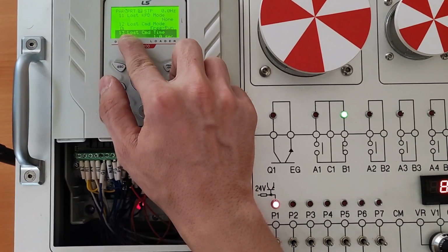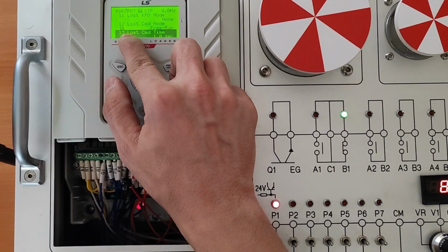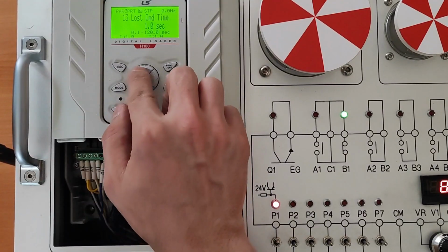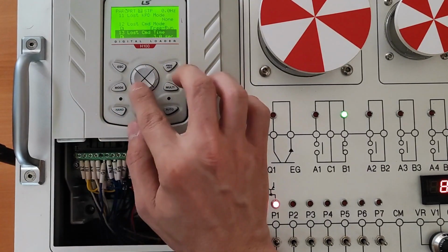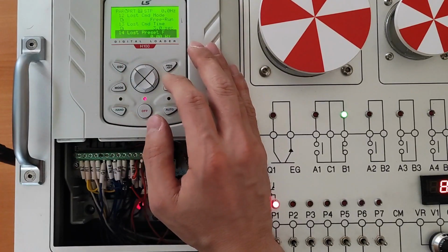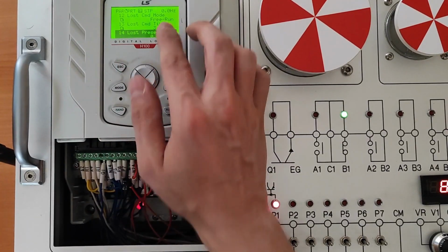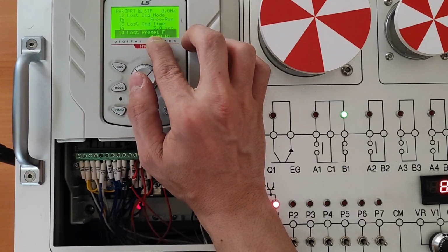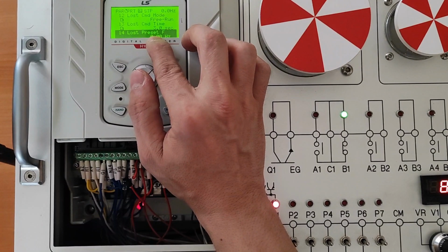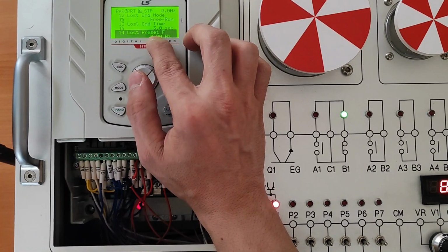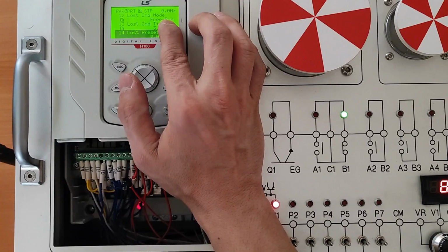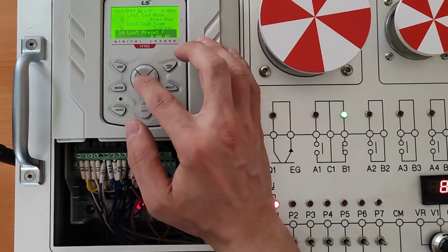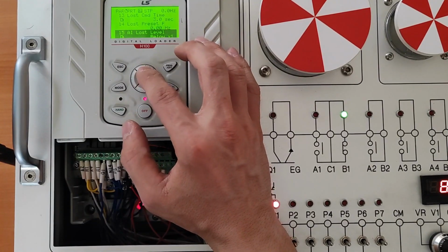I specify how many seconds it should wait before giving me the lost command error. So for example, I set the time to 3 seconds. In PRT 14, we previously mentioned that if we set the PRT 12 parameter to a value of 5, and that event happens, at what exact frequency should the inverter operate? Here, since we have already set it to the free run mode, which means the output will be completely disconnected, we do not need to configure the PRT 14 parameter at all.